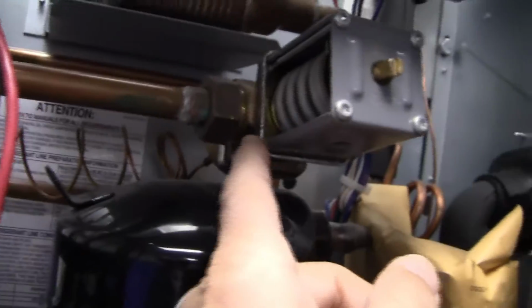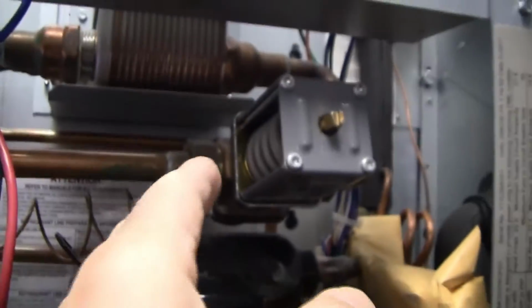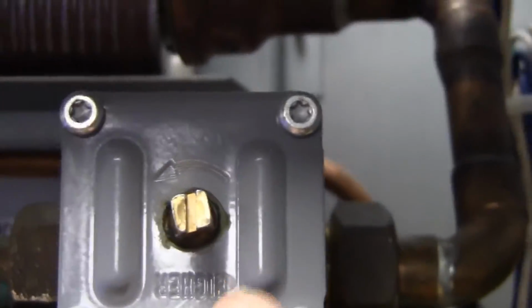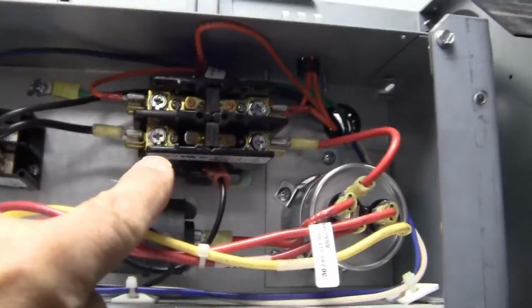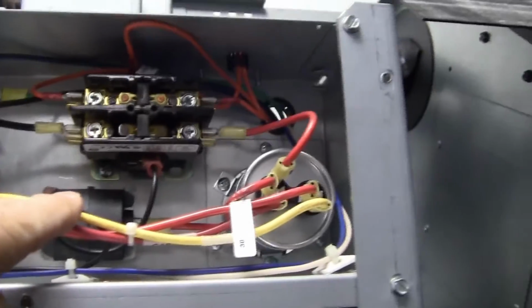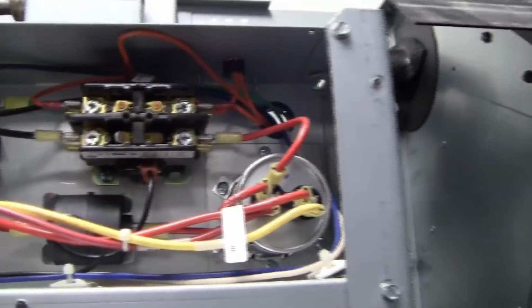But this is controlled by this spring-loaded valve, which has a pressure switch located right here in the line for the refrigerant. So this way it can modulate the flow according to the refrigerant pressure, and it's adjustable. There's a spring tension right here with which you can adjust that in order to maintain it. But that's not my issue. My issue today is just simply this two-pole contactor coil. No big deal. We'll have that changed out in a few minutes.